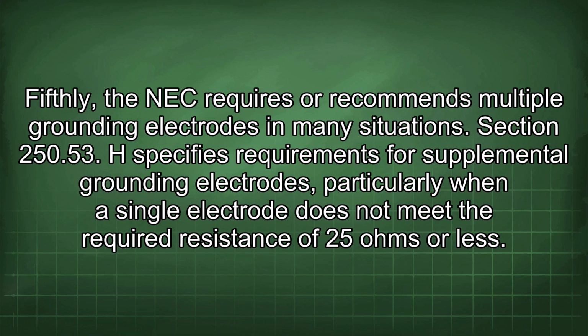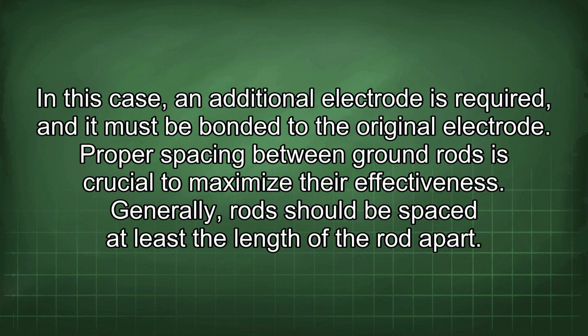Fifthly, the NEC requires or recommends multiple grounding electrodes in many situations. Section 250.53(H) specifies requirements for supplemental grounding electrodes, particularly when a single electrode does not meet the required resistance of 25 ohms or less. In this case, an additional electrode is required and it must be bonded to the original electrode. Proper spacing between ground rods is crucial to maximize their effectiveness.